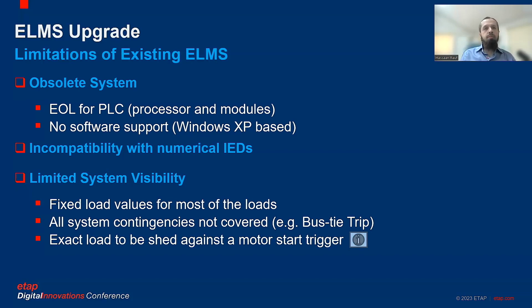Another issue with the software was that there was no idea of the exact load which will be shed against a trigger in case of a motor start. To explain this, whenever a TG tripping takes place, all the standby loads get interlocked, except the essential service motors. These are those motor loads which must be allowed to start at any cost. So whenever there is a start signal of any such motor with a TG down, there is a need of additional load shedding because we don't have any reserve at that moment. So that was being managed with this motor start trigger.